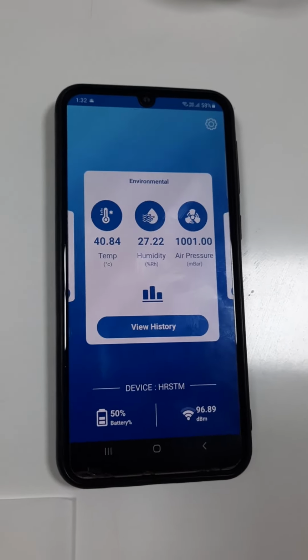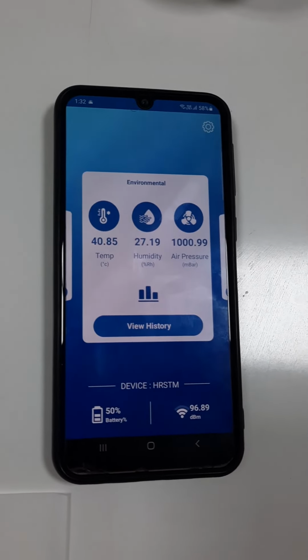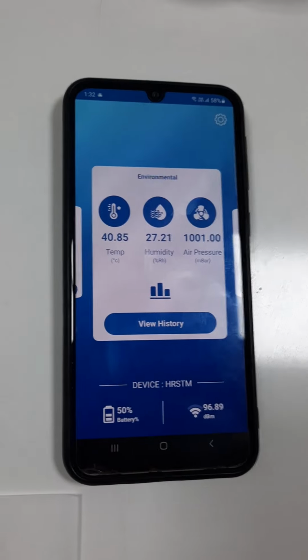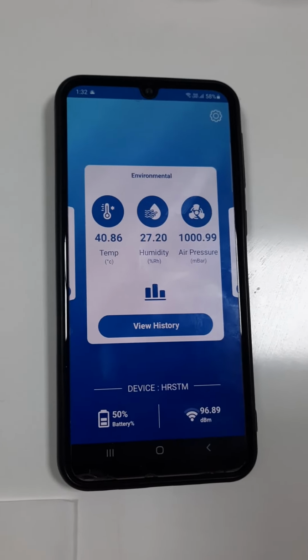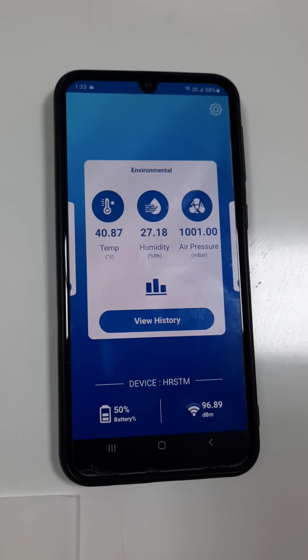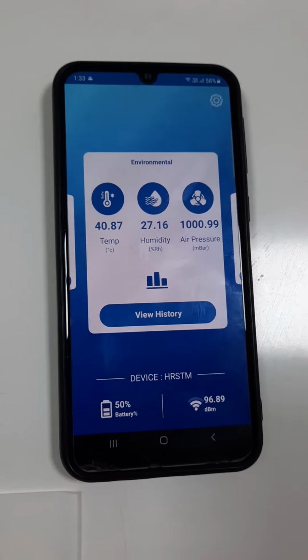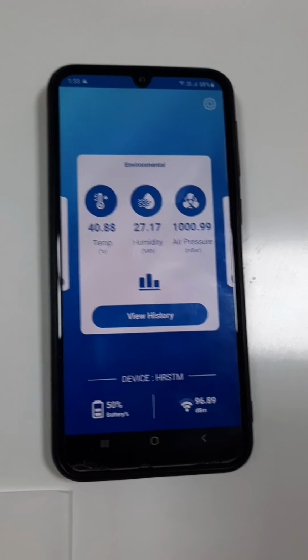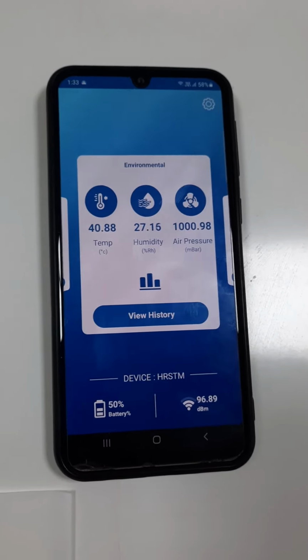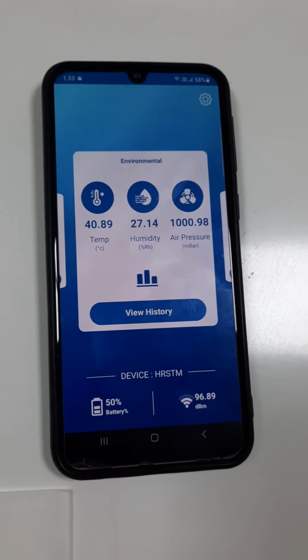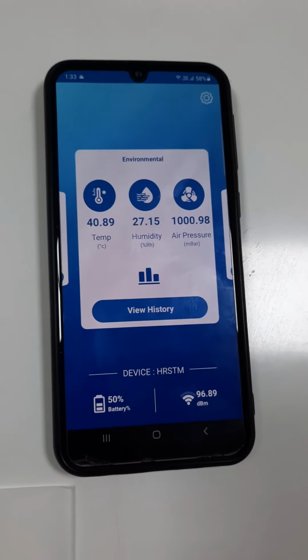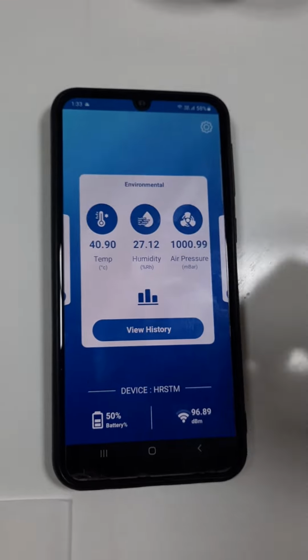But our main intent is to sense the internal temperature and the internal humidity of this device, which we can use for the correlation or the correction of the gas data, right? So it's not ambient temperature or humidity data, but data which is coming from inside this device. Now let's move to the very next slide.